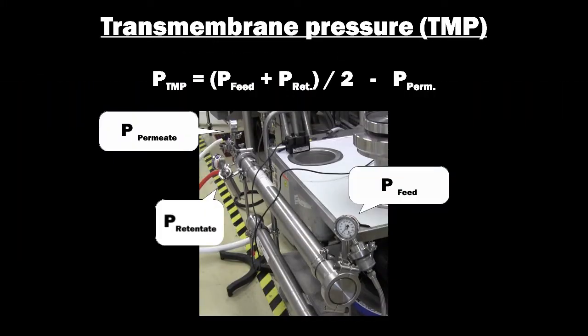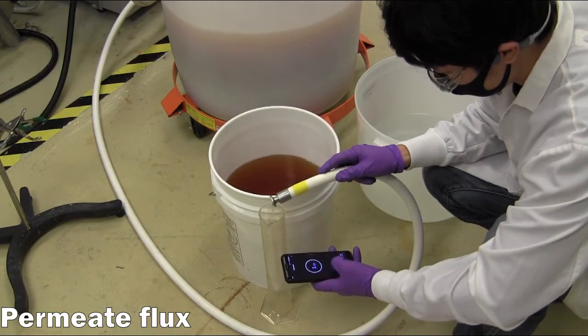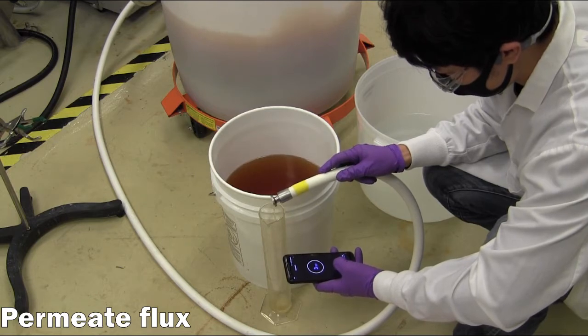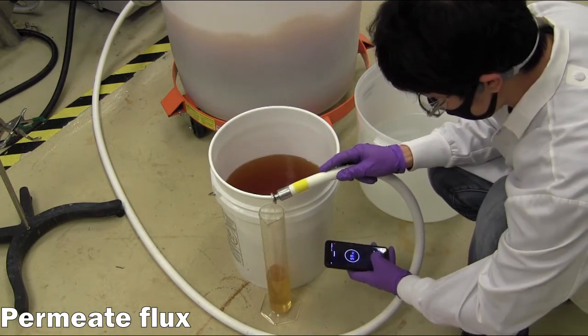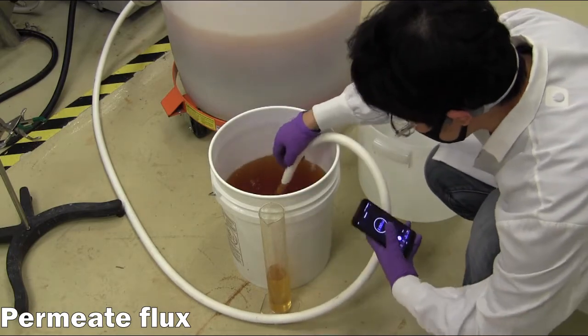The transmembrane pressure or TMP is the measured difference between the permeate stream and the cross flow stream pressures, the latter of which is calculated using the average of the feed inlet and retentate outlet pressures. This yields an effective measure of the driving force between the two sides of the membrane. Permeate flux will generally increase as the TMP is increased at the expense of increased accumulation of material that may ultimately lead to membrane fouling.